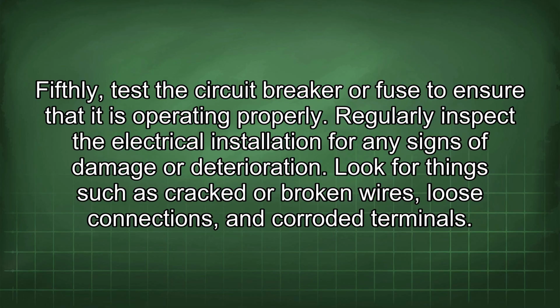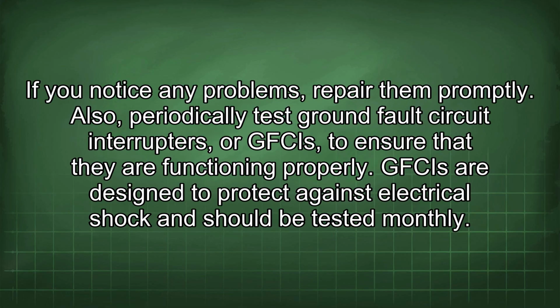Regularly inspect the electrical installation for any signs of damage or deterioration. Look for things such as cracked or broken wires, loose connections, and corroded terminals. If you notice any problems, repair them promptly. Also, periodically test ground fault circuit interrupters, or GFCIs, to ensure that they are functioning properly. GFCIs are designed to protect against electrical shock and should be tested monthly.